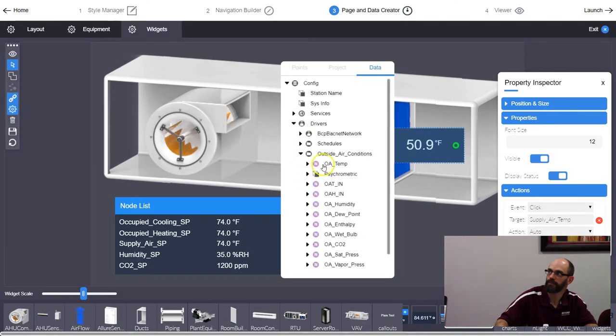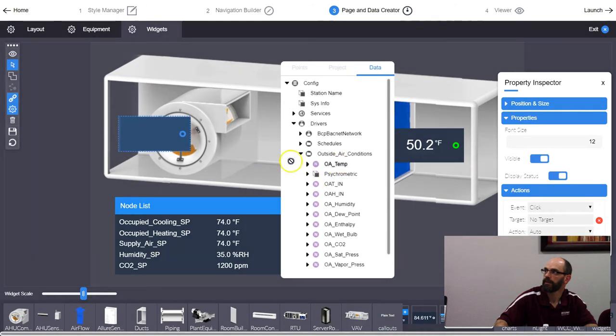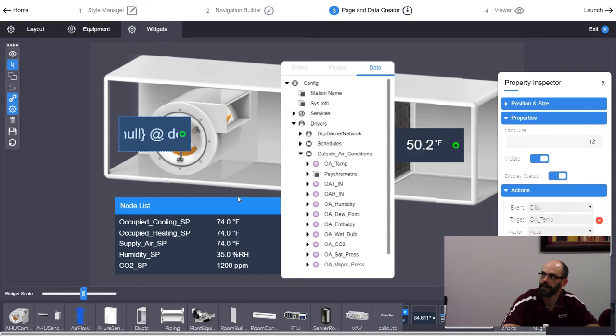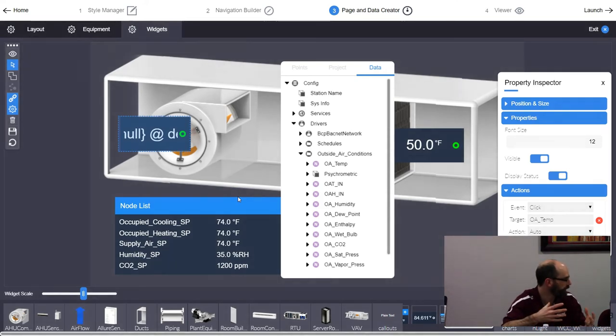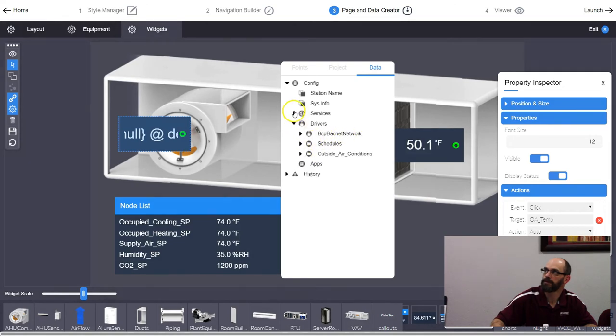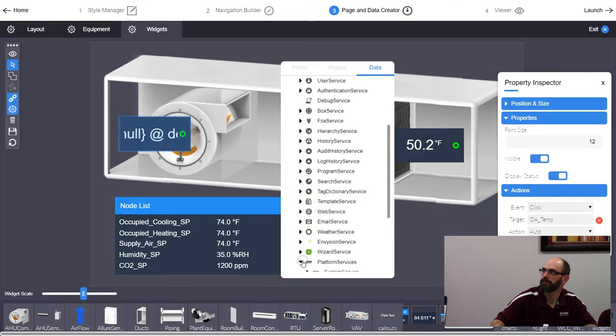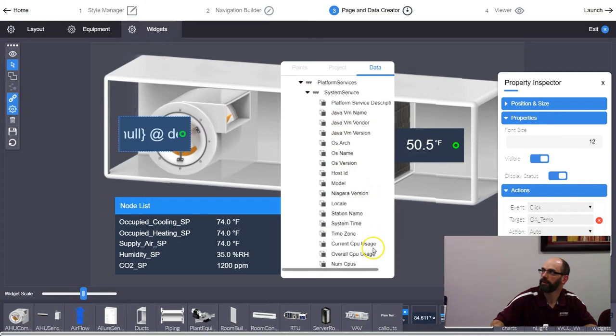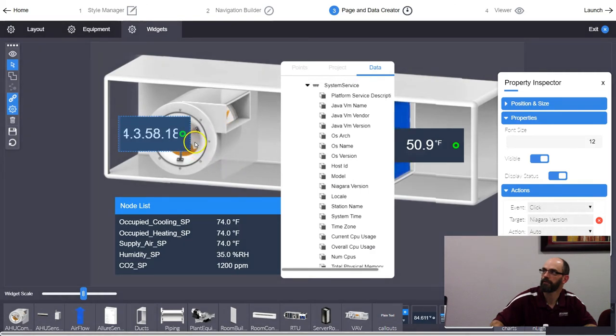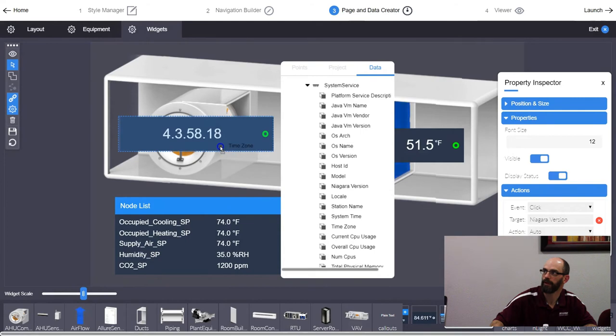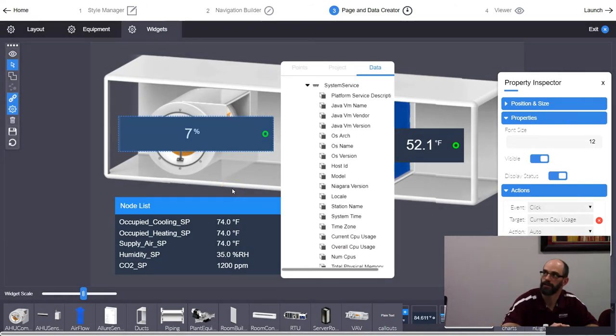For example, if I want to show outside air temp, I can pull it from the data tree. That point will never relativize to a new node — it'll always show outside air temp from that one fixed point. But here's what's neat: you can now pull information you never really could before. You can pull platform services data — Niagara version, time zone, current CPU usage — and display it right on the graphic.